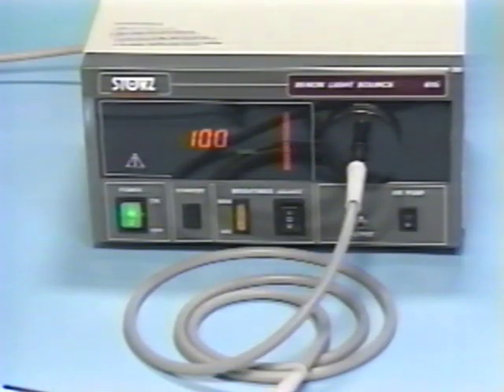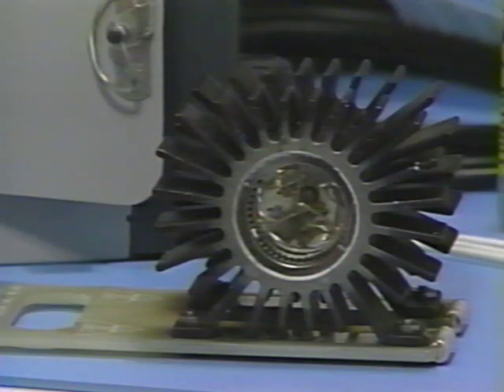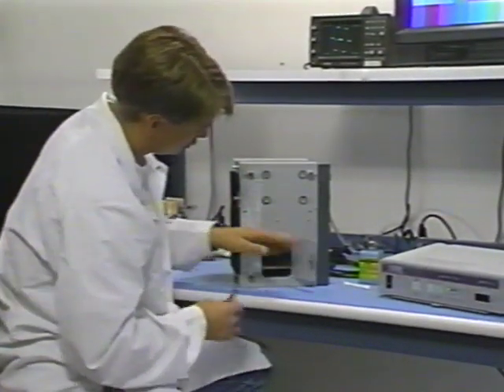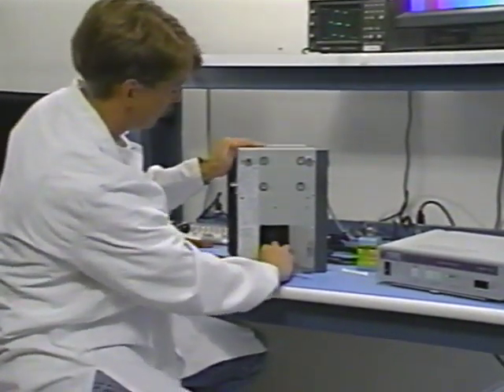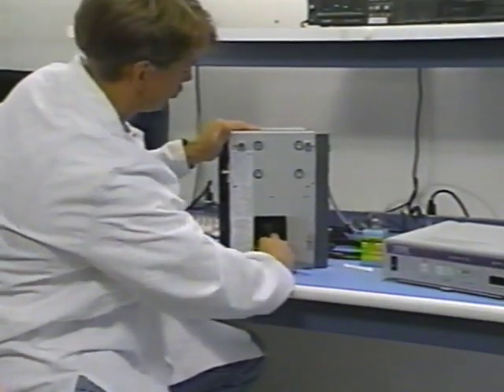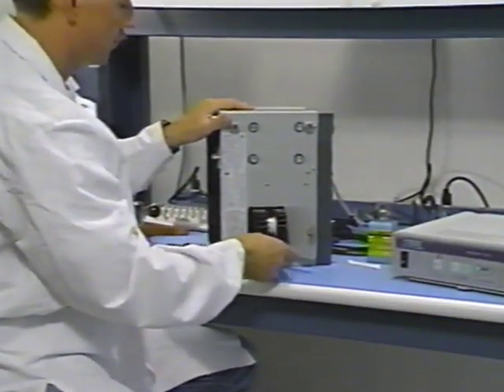The light source provides the illumination necessary to perform endoscopic surgery. An aged lamp or malfunctioning system can cause inadequate illumination for the entire imaging system. Generally speaking, lamps should be replaced before they have reached the maximum hours stated by the manufacturer or when light drop-off is noticeable. Light guide cables carry the light from the light source to the endoscope. These cables are somewhat fragile and, if not handled with care, can be damaged.